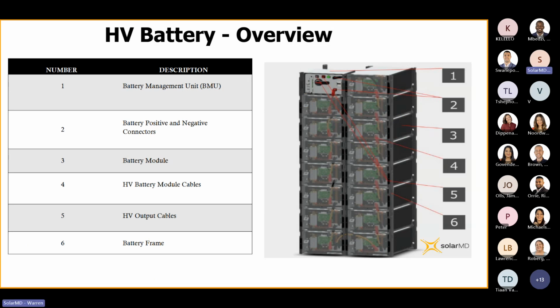Here's a breakdown of the high voltage battery itself. It's not really any more complex than any one of the low voltage solutions, there's just more components involved. All the battery modules are connected in series to one another. Each battery module is fused, and inside the BMU there's a larger single fuse as well, so there's plenty of protection in place. You've got a manual on-off switch and an internal relay that we can activate if necessary. All of these individual battery modules communicate amongst themselves and report their collective data back to the BMU.